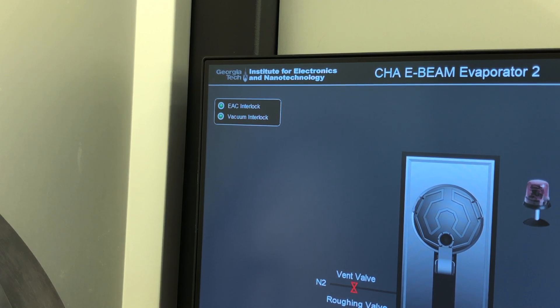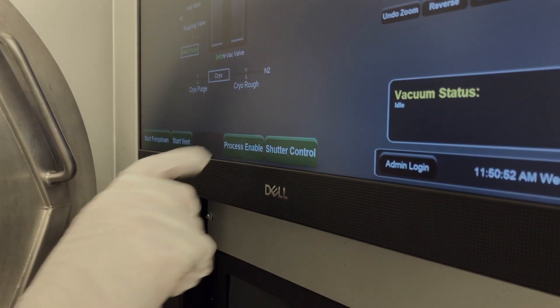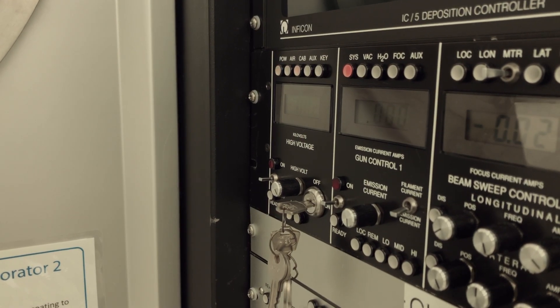If you want to run your process at a low pressure, it may take approximately 30 to 45 minutes to pump down. When the desired pressure has been reached, click the enable process icon on the monitor. The red lights below the deposition controller should illuminate.